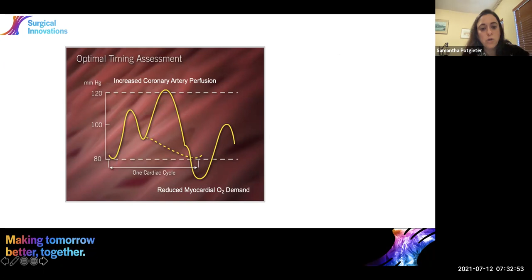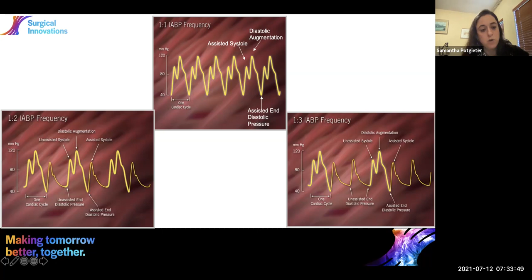So I'm not going to live too long in terms of timing or optimal timing assessments. You just need to understand what you are looking at. And what is very important for you to know is when your therapy is on a one-to-one frequency, you cannot tell the difference between the augmented pressure, the balloon, and the patient. You can only tell which is the patient and which is the pump in a 1-to-2 frequency or in a 1-to-3 frequency, where you see the presence of the dicrotic notch. Otherwise, it's too confusing. So the different frequencies that are available are in terms of how much support you're wanting to give the patient. But when you're looking at timing and you're trying to assess whether the delivery system is correct and whether you are in fact helping the patient, you have to move into a 1-to-2 or a 1-to-3 frequency to determine which is the patient and which is the pump, if you were concerned about timing.